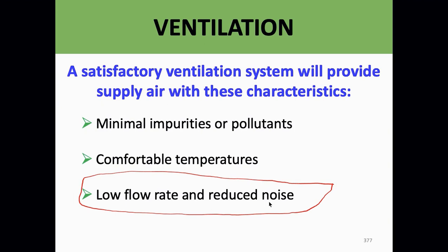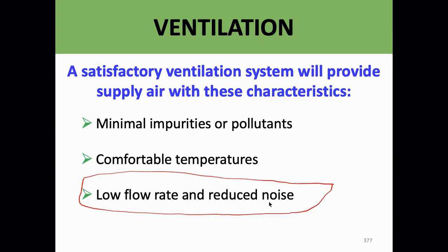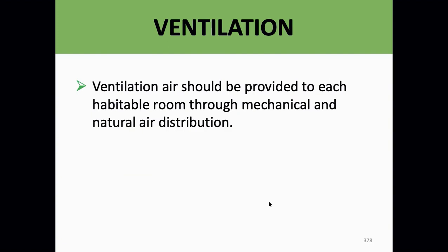A good ventilation system provides minimal pollutants, comfortable temperatures, and low flow rate with reduced noise. The lower the air exchange rate, the less noise I'll have. If you're designing a place, can't you go slightly larger on the ductwork to get more air exchange with less sound? Absolutely. What we're calculating when we do ductwork design is the minimum. I can drop the static pressure by going to slightly larger ductwork, drop my velocity in feet per minute, and cause the system to work more efficiently.